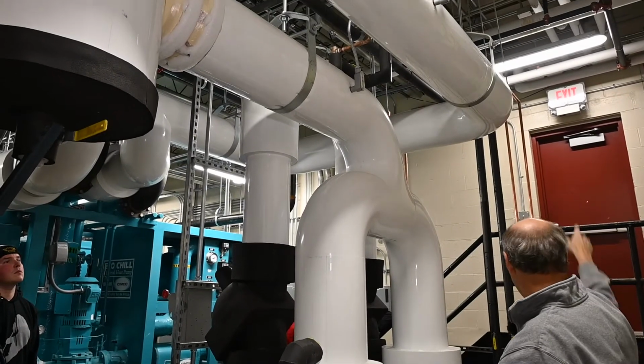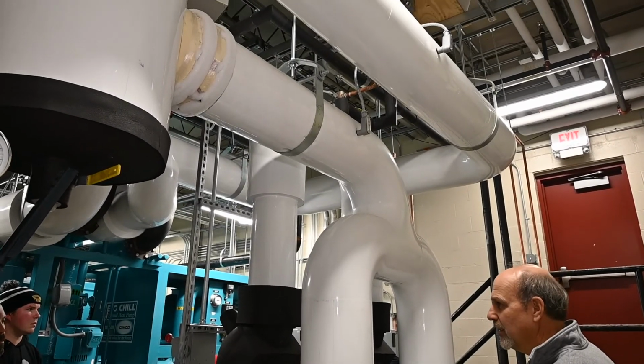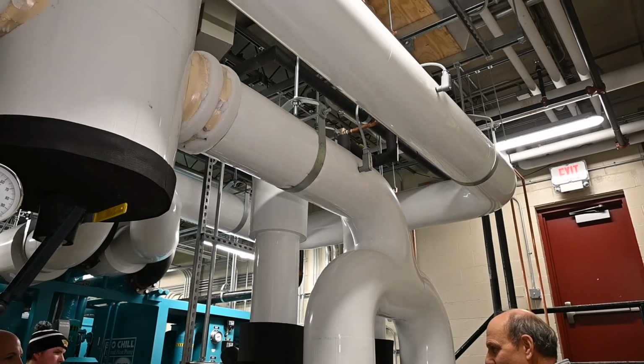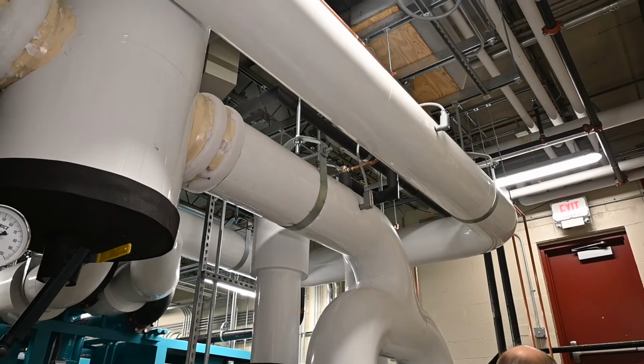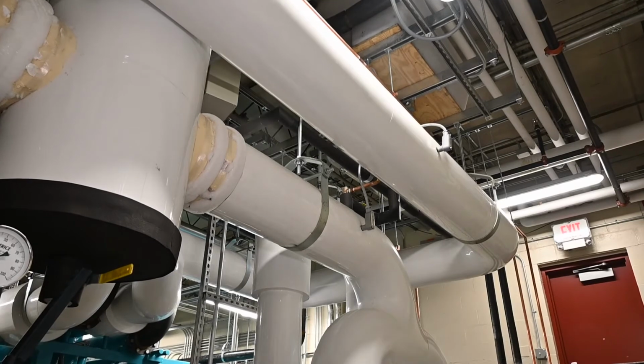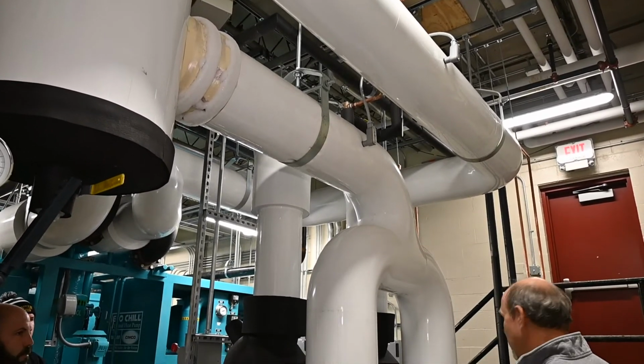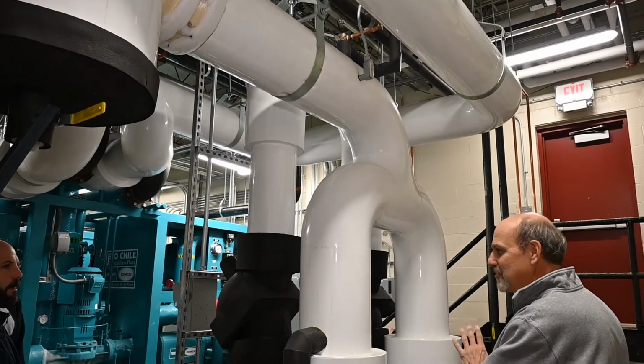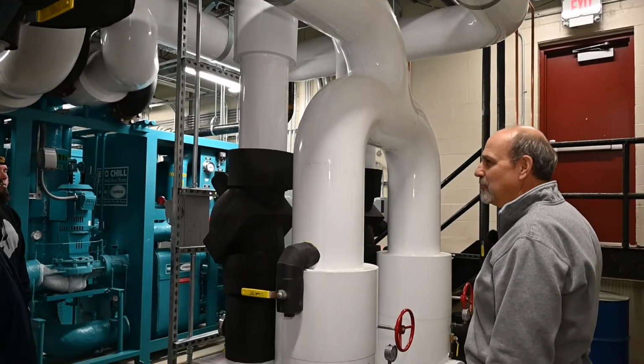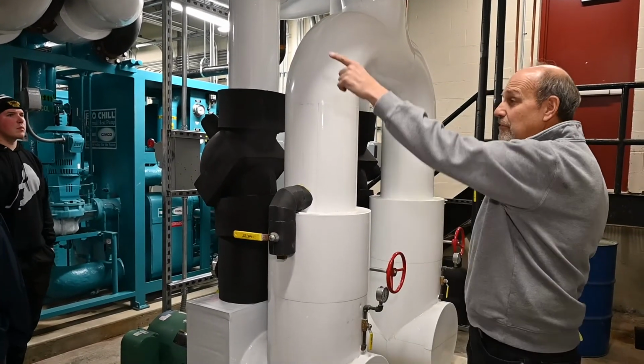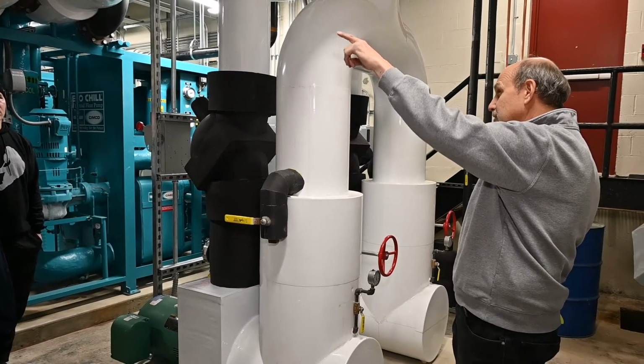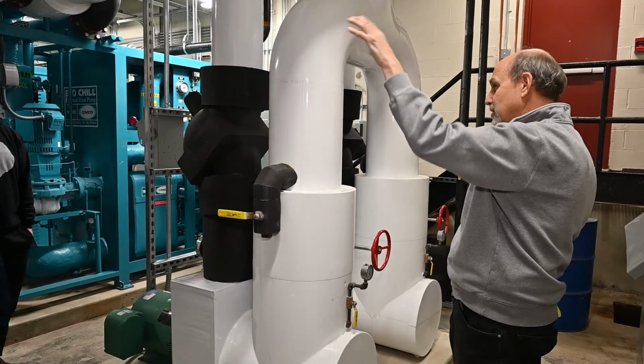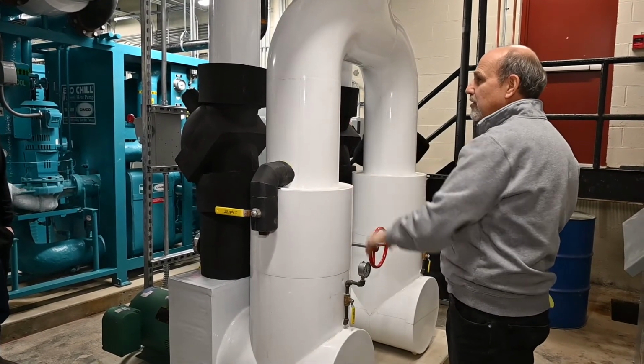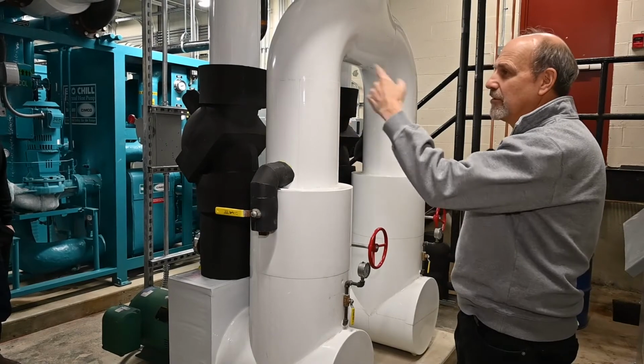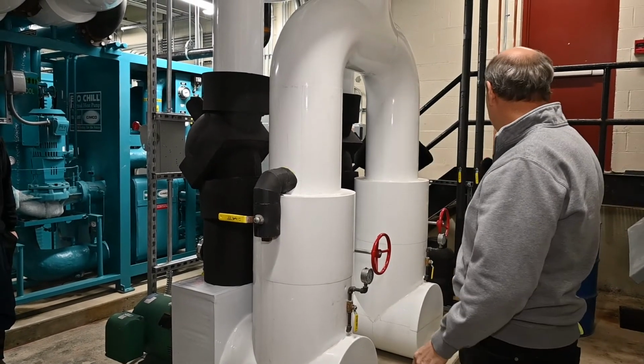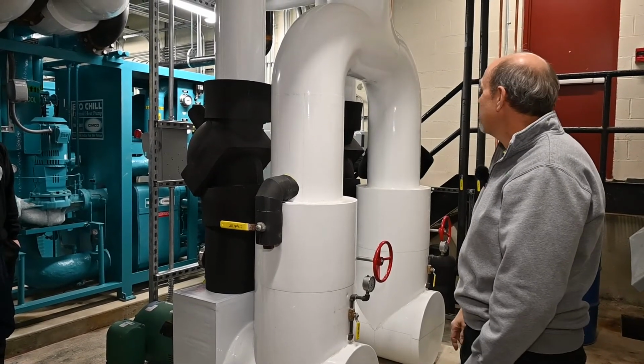So we've piped that over to a 55-gallon drum here, so we're not dumping glycol on your floor. It at least dumps it in there. So that should never be full, and it's something you might want to check just by shaking the barrel, and if it's empty, that's a good thing, because there's no reason that there should ever be glycol in that tank. Same thing for the warm loop. That's set at 50 pounds, because we're running a little bit higher pressure in the condenser loop than in the glycol cold loop, but same theory. If it gets too high, it'll open up and dump into that holding tank.